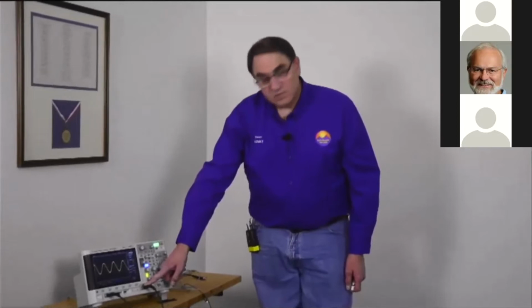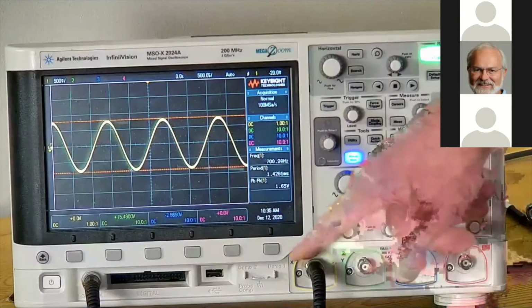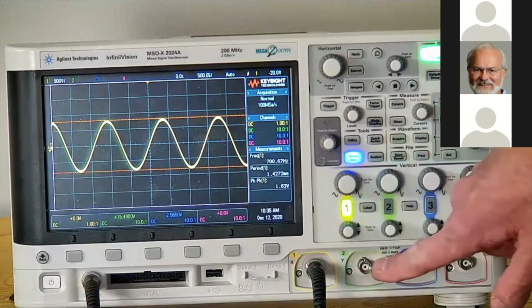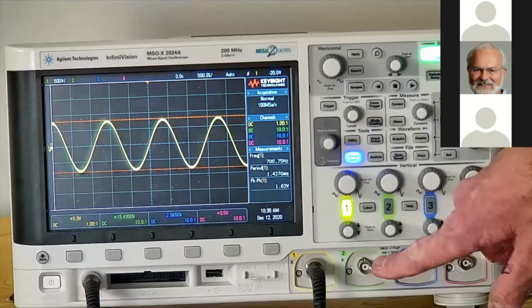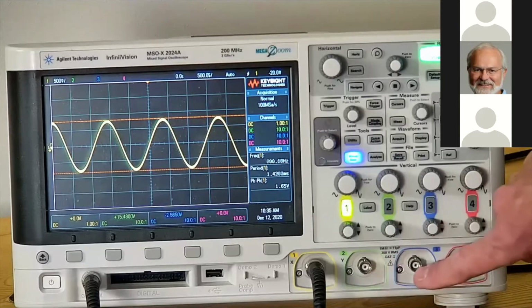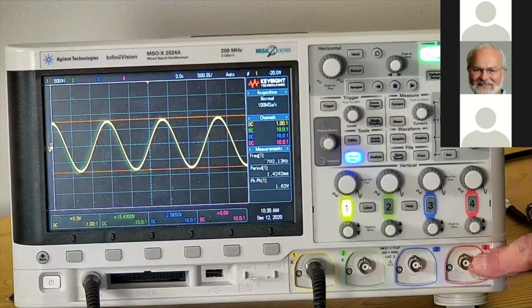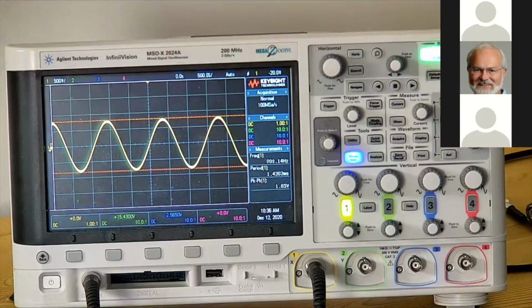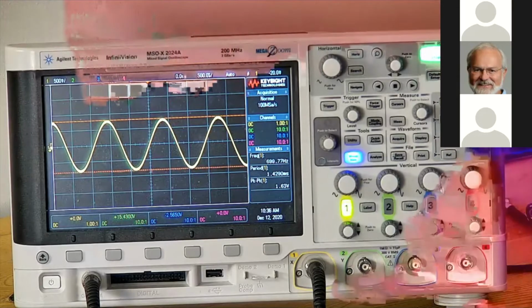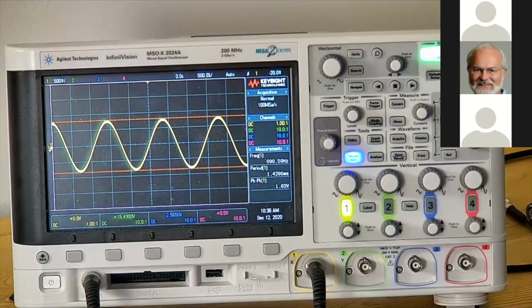And having a 4-channel scope would let us look at the trigger, the exciter being triggered, and the switching in the intermediate amplifier to make sure that it's happening at the right time. And then we could also look at the high voltage waveform, and put a current probe on that 80 kilovolt input and look at a current waveform, line all those traces up, and see that we had the required 1.5 microseconds from the first operation to the next, to the third, to the fourth. And that's why we might use 4. So that's just one example. But of course, you have your own.